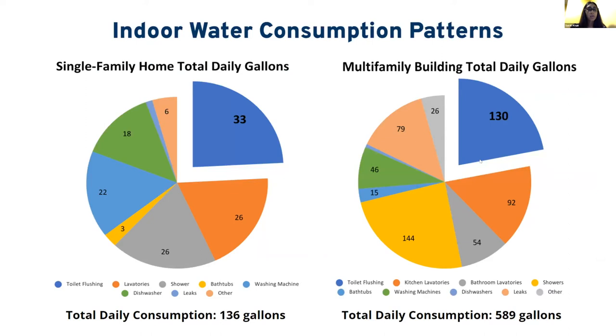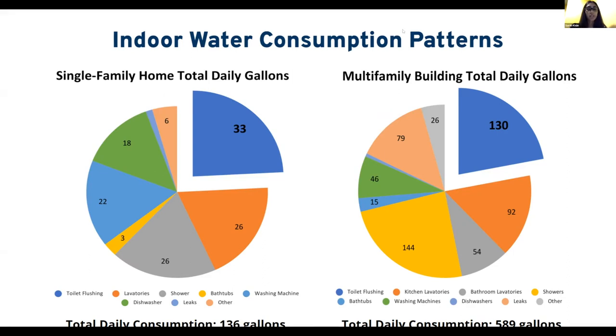Now we have indoor water consumption patterns for both dwellings. The pie charts show consumption broken down by the various household uses, and the highest demand was found in toilet flushing for both the single-family home at 33 gallons and the multi-family building at 130 gallons daily. Total daily indoor consumption, excluding yard water usage, adds up to 136 gallons daily in the single-family home and 589 gallons daily in the multi-family building.